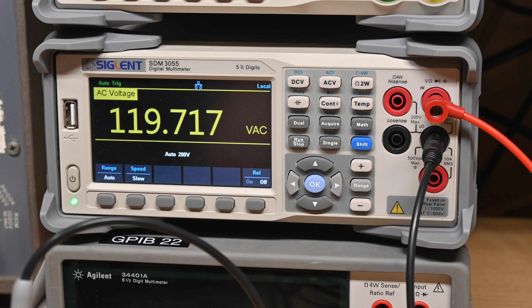All right, I don't have a neutral exposed inside the chassis, so I don't have a good place to clip onto, so I'm going to slip this probe here into the socket and show you the AC voltage, and this is after the CL80 with the thing powered on. It's been on for about 5 minutes. So we're seeing 117.5 volts, which is great because we're at 120 coming out of the AC power source. Actually, let me show you. Let me move this to the other side here, and I'll show you that 120. There we are, well, 119.7.